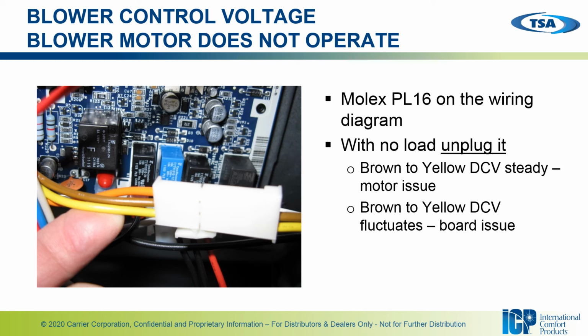So, troubleshooting the variable constant torque motor, you'll have a Molex plug number 16 on the wiring diagram. It will come directly off the board and go to the motor. There will be a junction point between the motor and the control board. You should see a brown and yellow wire and even an orange wire on one side.